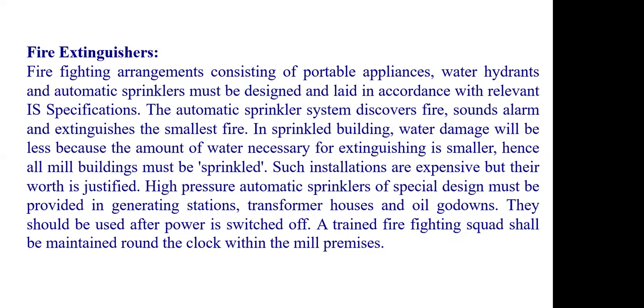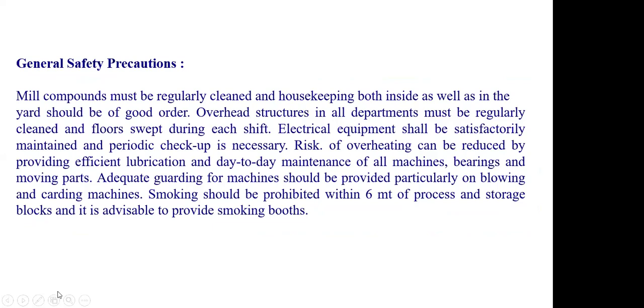High pressure automatic sprinklers of special design must be provided in generating stations, transformer houses and oil godowns, and they should be used after the power is switched off. Also, a trained firefighting squad shall be maintained around the clock within the mill operations. A trained firefighting squad means trained firefighters. So they should be around the clock; in every shift we should have a certain number of people trained in firefighting activities.